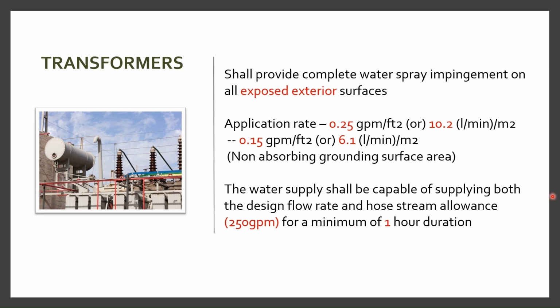So the transformer, for example, if you look at this particular figure, will be sitting on concrete pads beneath the transformer. So that area shall also be covered with a design density of 0.15 GPM per square feet, and no piping across the top level or across the face of the cabinet or access. This is also a consideration. And the spray nozzles shall be provided in such a way that they do not obstruct any of the energized parts of the transformer. So electrical clearances will also be available in NFPA 15.